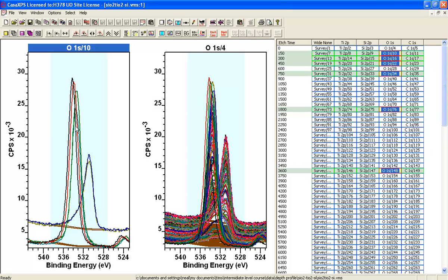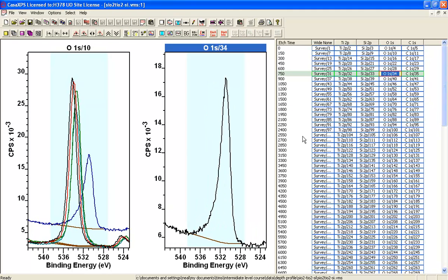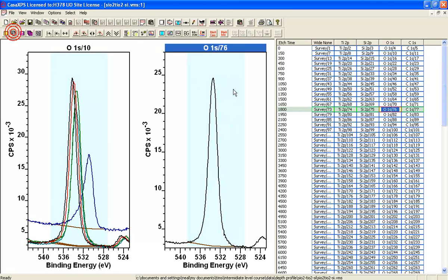So a linear least squares applied to a silicon oxide layer in this particular experiment would not work well if we chose just a single peak. However, the titanium will work reasonably well with one representative peak for the titanium. So what we will do is we will find a titanium peak, and let me just see that that one is, that's the titanium that I was interested in, whereas that one is a silicon.